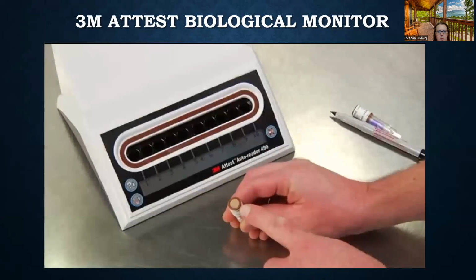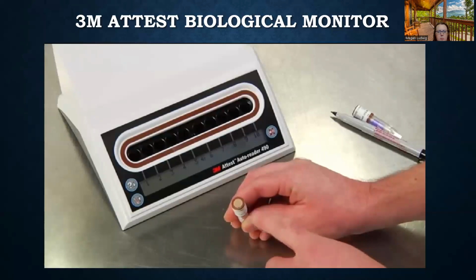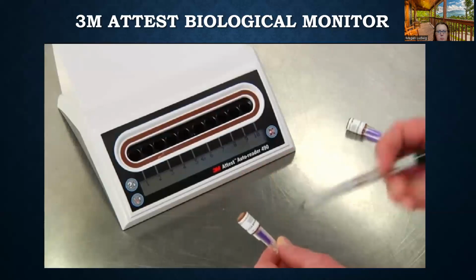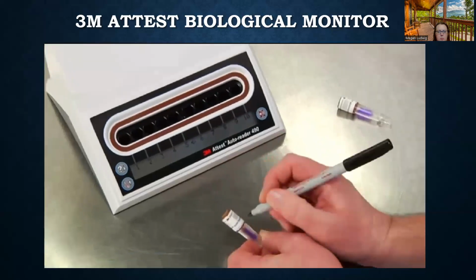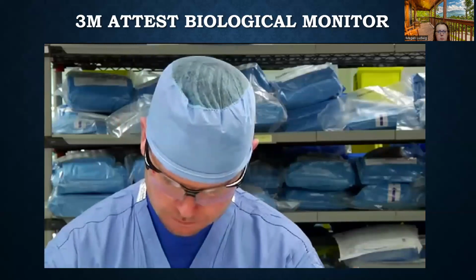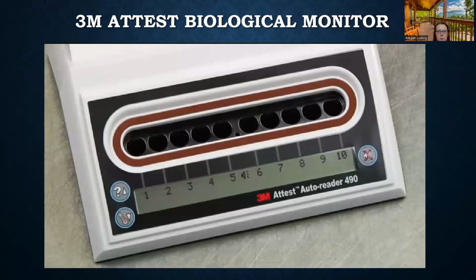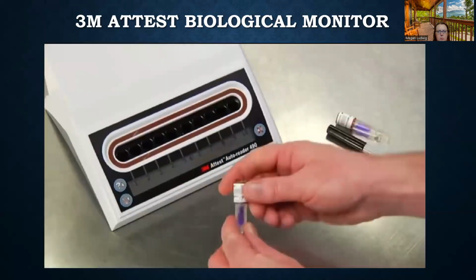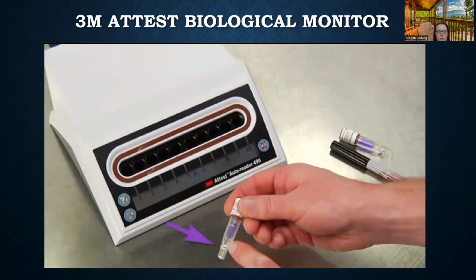Open the challenge pack and allow the Attest Super Rapid BI to cool for 10 minutes before activating. Check the process indicator on the cap of the BI. A color change from pink to light brown confirms that the BI has been exposed to the steam process. Be sure to label the BI with the sterilizer, load number, and date. Wearing safety glasses, place the Attest Super Rapid BI in a matching color-coded Attest Auto-reader 490 incubation well. Make sure the flat side of the vial faces the back of the auto reader.